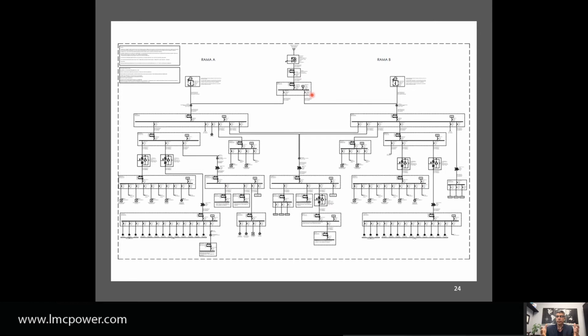In this case, we have a very big customer, so a lot of losses could occur. They decided to go with the highest kA rating, 500 kA. They figured that as long as they protect against any kind of lightning, they're good. The difference between a 300, 400, or 500 kA is just a couple hundred dollars, so they said put in the biggest thing you've got.